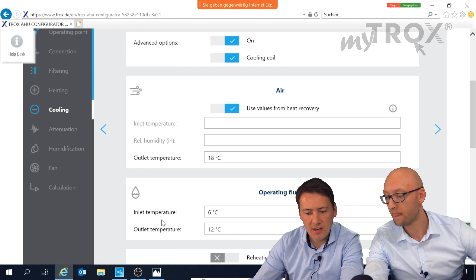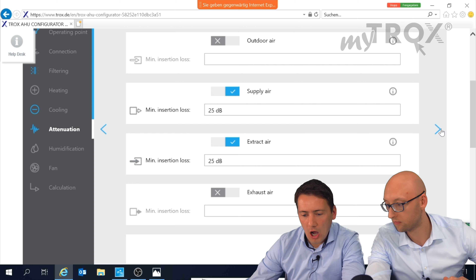Next is attenuation. Was there anything mentioned about sound? Yeah, the sound power shall be reduced on the building side. That means in the outdoor air we might work without any silencer, and also in the exhaust air. So we keep the silencers in the supply and extract air, and also the minimum insertion loss of 25 dBs.